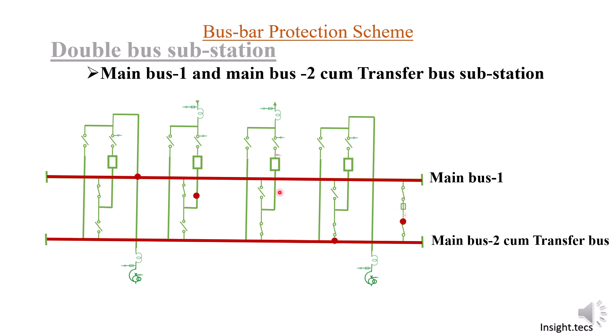Now, what happens when a circuit breaker is under some kind of fault or requires maintenance? In that case the breaker is open, so you will not be able to charge this particular bus from that line equipment, but the bus will still remain charged due to the bus coupler circuit breaker. However, suppose you want to inject power through that line due to grid loading requirements — in that case we can use the main bus cum transfer bus scheme.